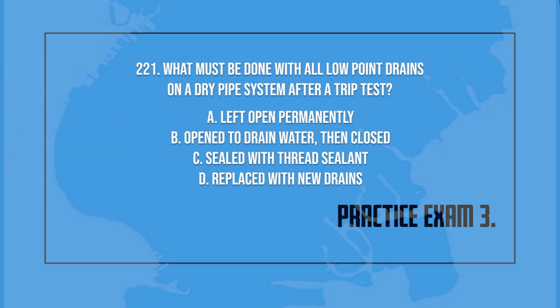(221) What must be done with all low-point drains on a dry pipe system after a trip test? A. Left open permanently. B. Open to drain water, then closed. C. Sealed with thread sealant. D. Replaced with new drains.